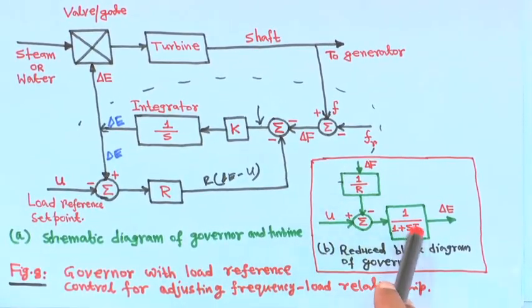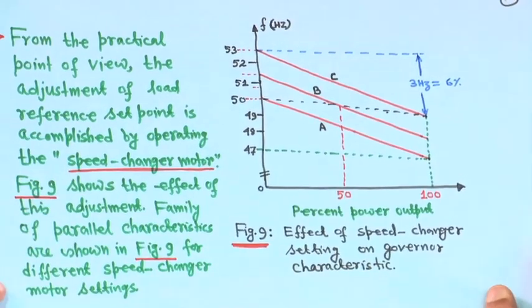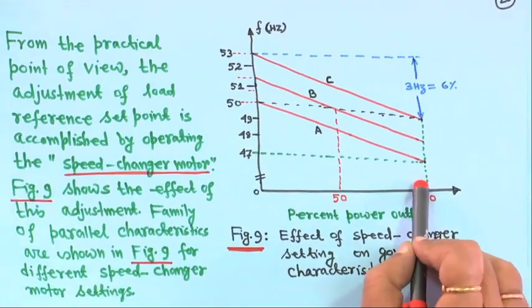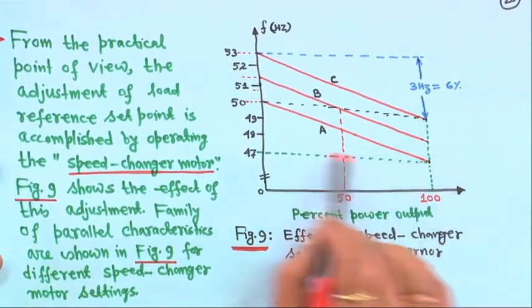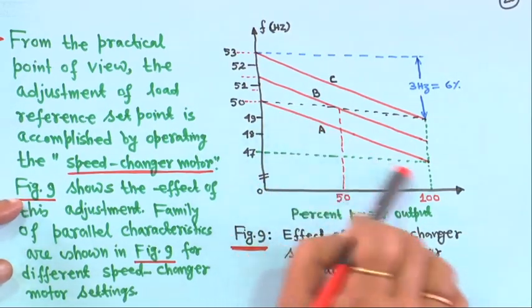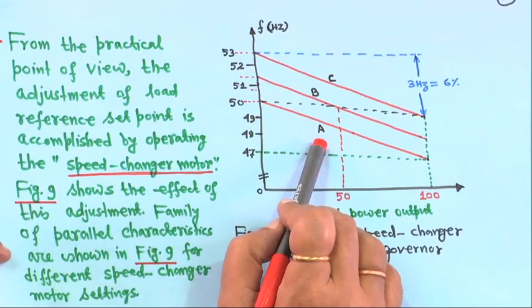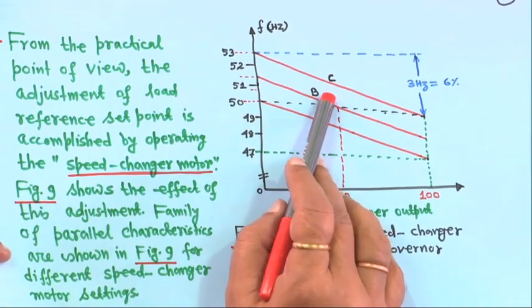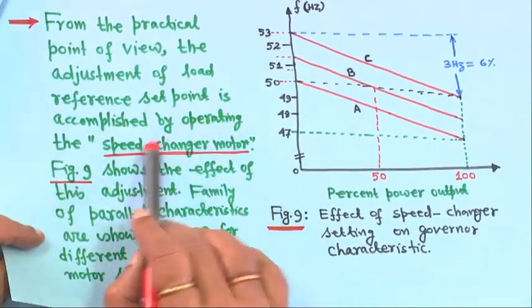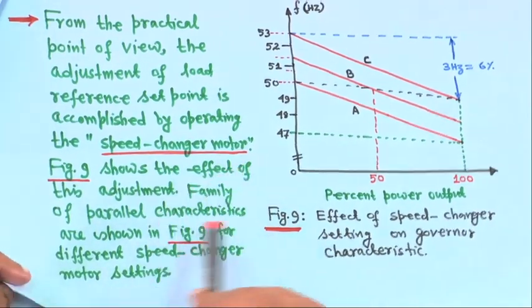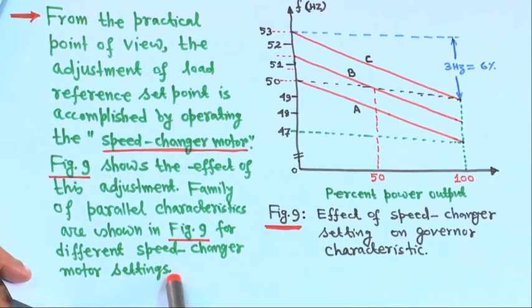I have already shown you how to make it. Suppose you have 3 units in a 50 hertz system with 3 different droop characteristics for 3 different generating units. From the practical point of view, the adjustment of the load reference set point is accomplished by operating the speed changer motor. Figure 9 shows the effect of this adjustment — a family of parallel characteristics for different speed changer motor settings.